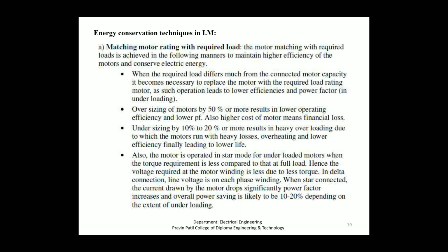Also, underloaded motors can be operated in star mode when the torque requirement is less compared to that at full load. Hence, the voltage required at the motor winding is less due to less torque. In delta connection, the line voltage is on each phase winding. When star connected, the current drawn by the motor drops significantly, power factor increases and overall power saving is likely to be 10 to 20% depending on the extent of underloading.